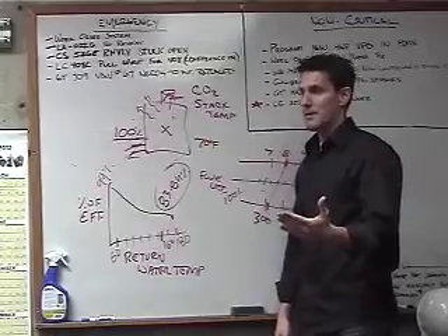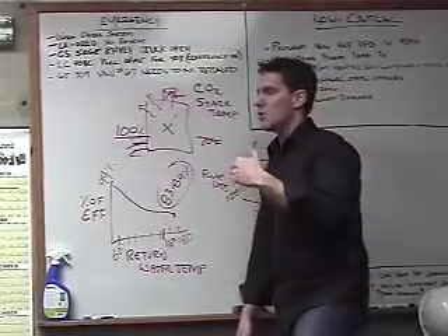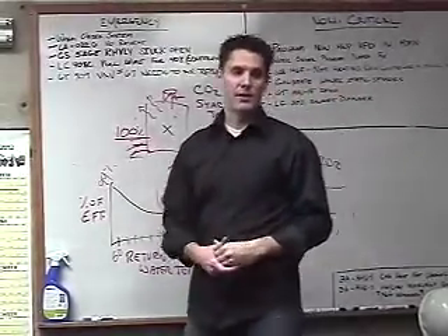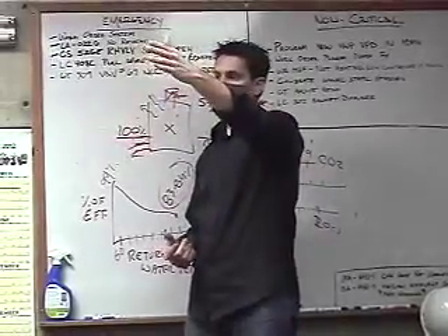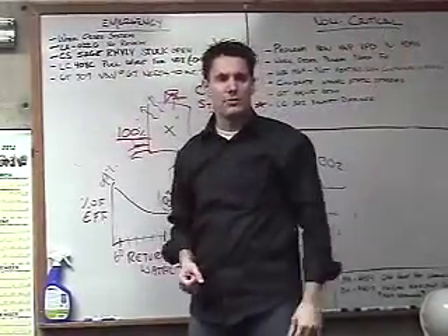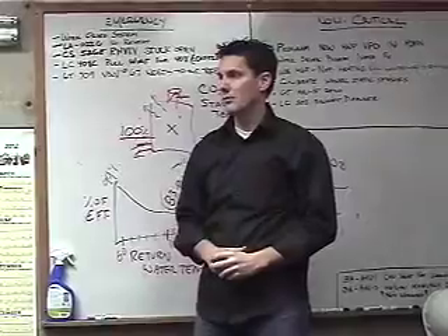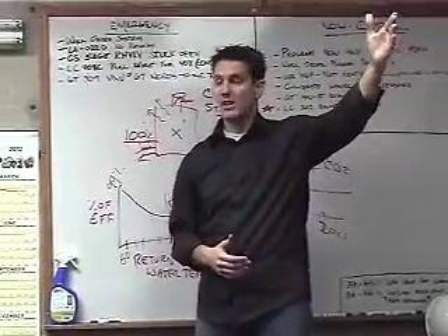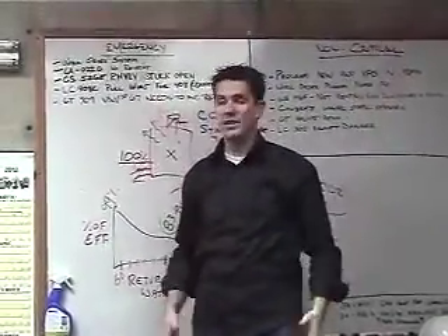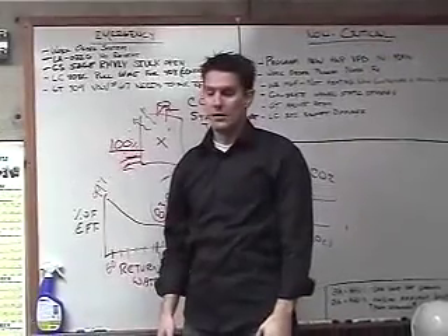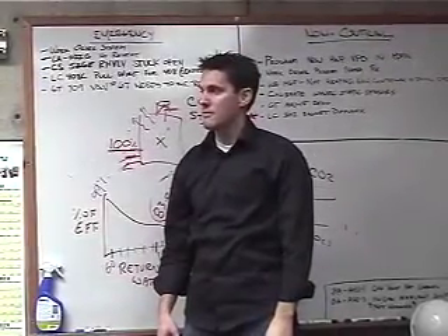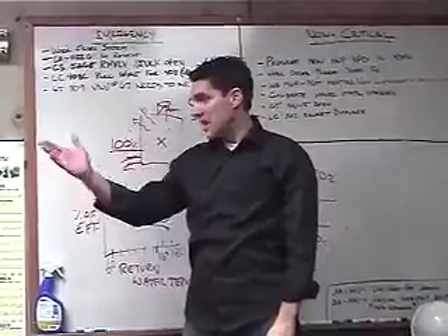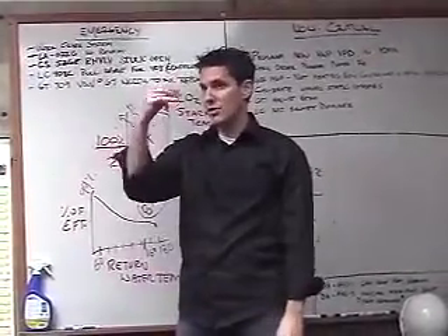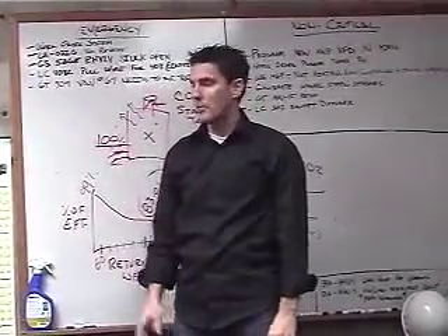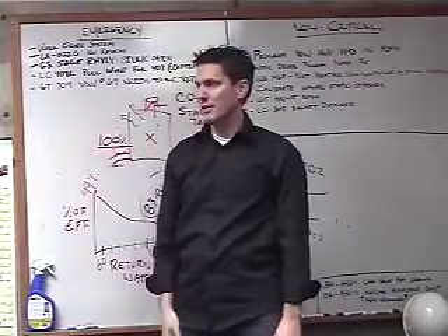You know why? What gives your boiler the permission to condense? Why is this boiler a condensing boiler, but a big old Cleaver Brooks fire tube boiler is not a condensing boiler? I used to condense on them all the time, but it's not. These are. What's the difference? That's heat exchanger. Maybe one less heat exchanger. This one does have 2 heat exchangers, but there's something about the heat exchanger.